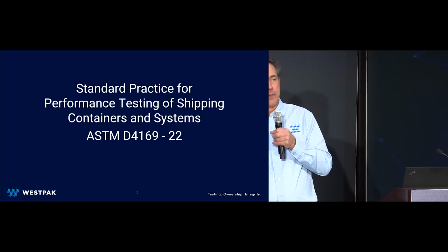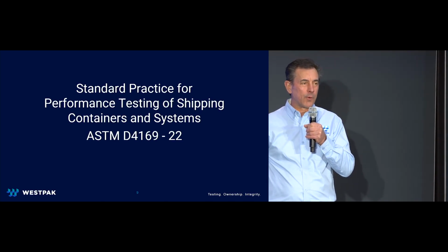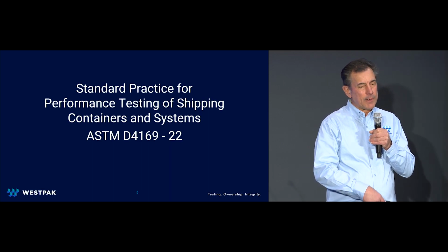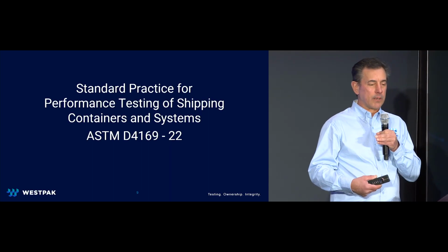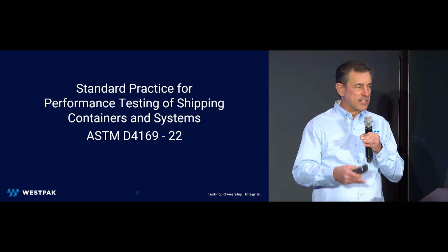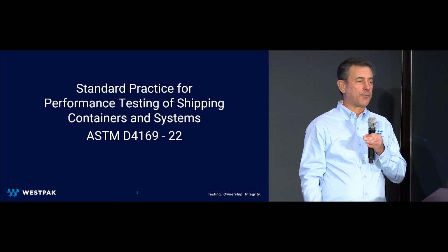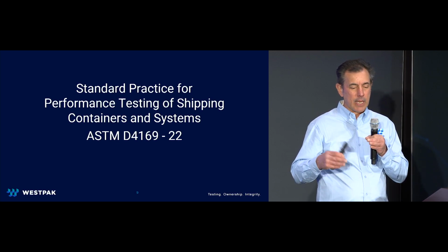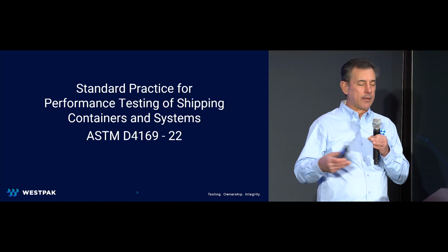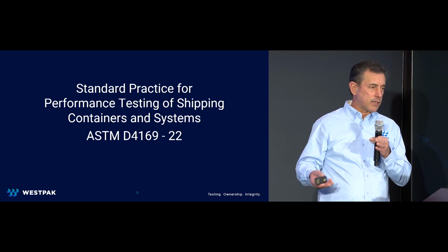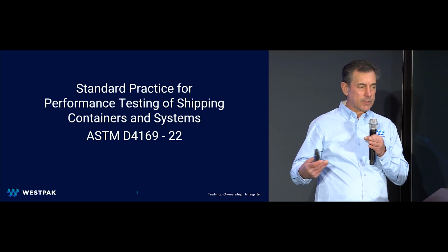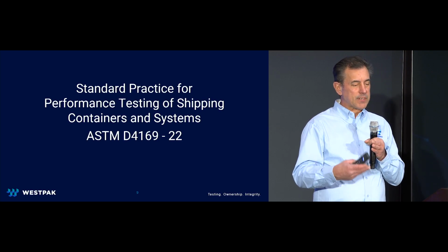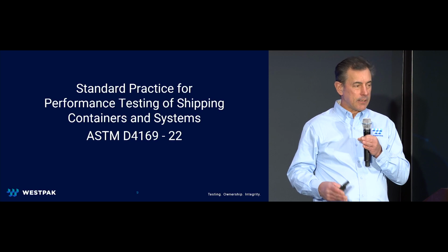Okay, the environmental conditions, how does that work with elevation was the question. So the environmental conditions are assumed to be kind of site conditions, and then we test for altitude conditions. The altitude condition is typically done at what we call a standard condition of plus 23 degrees C, or alternatively, the standard says plus 5 degrees C as well.